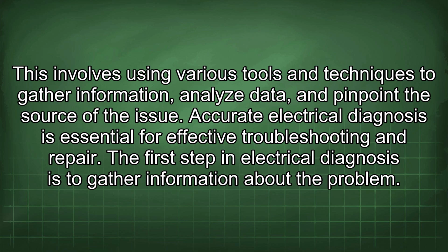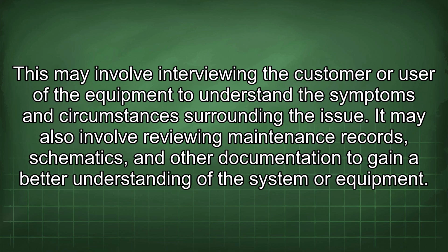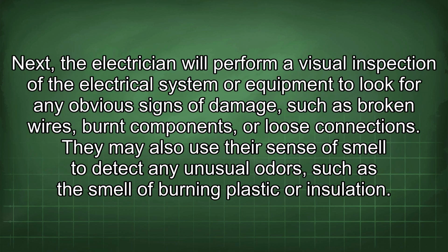The first step in electrical diagnosis is to gather information about the problem. This may involve interviewing the customer or user of the equipment to understand the symptoms and circumstances surrounding the issue. It may also involve reviewing maintenance records, schematics, and other documentation to gain a better understanding of the system or equipment. Next, the electrician will perform a visual inspection of the electrical system or equipment to look for any obvious signs of damage, such as broken wires, burnt components, or loose connections.